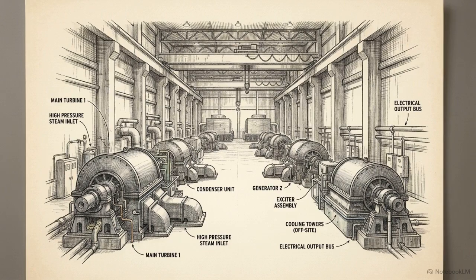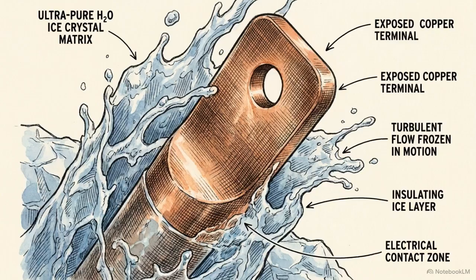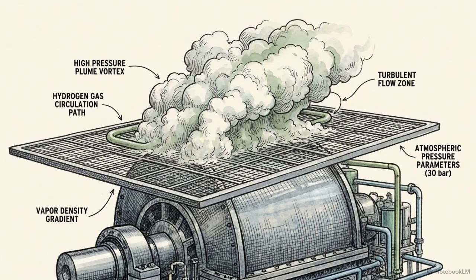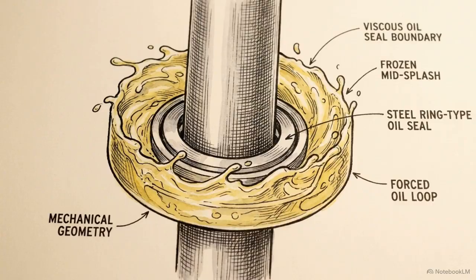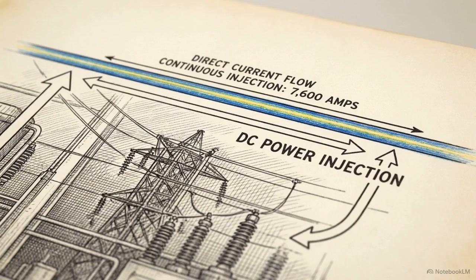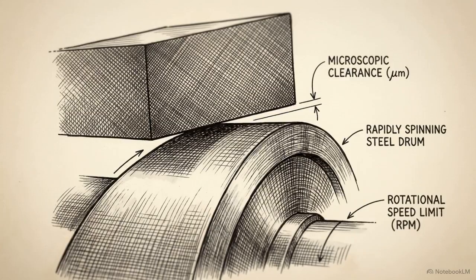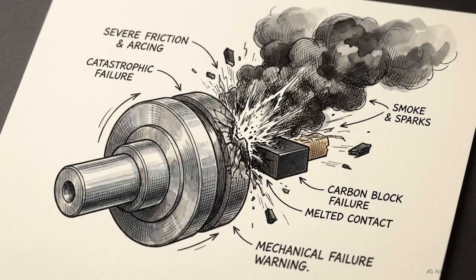Pushing a gigawatt of power relies completely on this simultaneous orchestration, isolating high-voltage copper with ultra-pure water, aggressively circulating pressurized gas, and sealing boundaries with forced oil. To induce the magnetic field, the main rotor requires a massive continuous injection of 7,600 amps of direct current at 400 volts. Transferring 7,600 amps from a stationary source into a steel mass spinning at 3,000 RPM using physical carbon brushes and slip rings would cause catastrophic friction and electrical arcing.